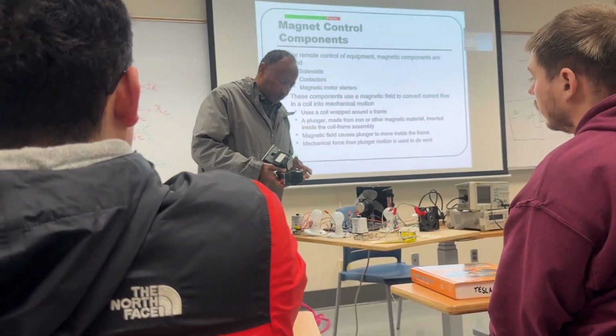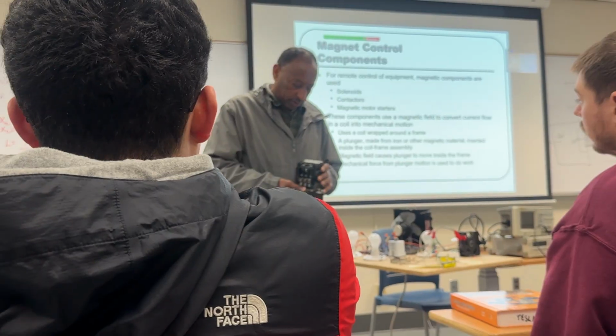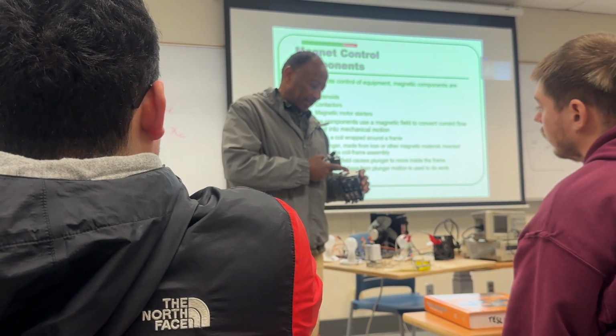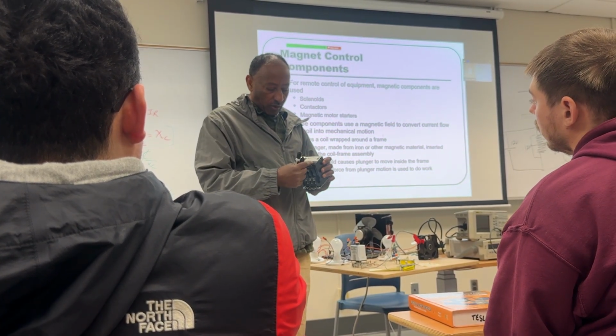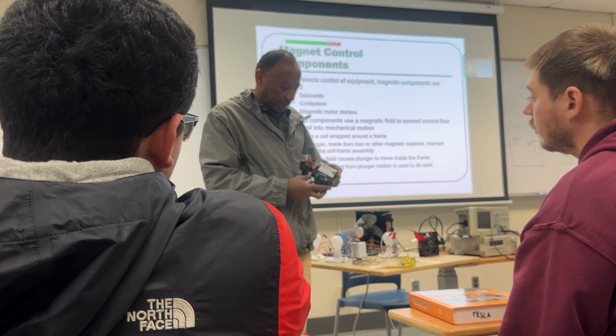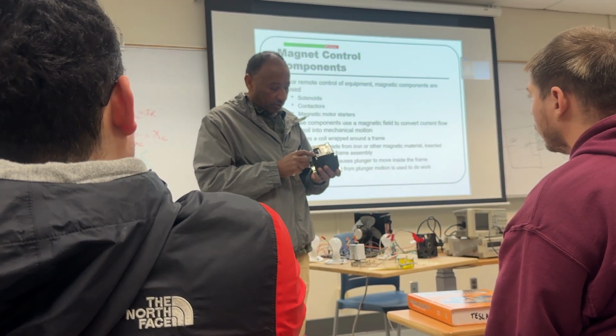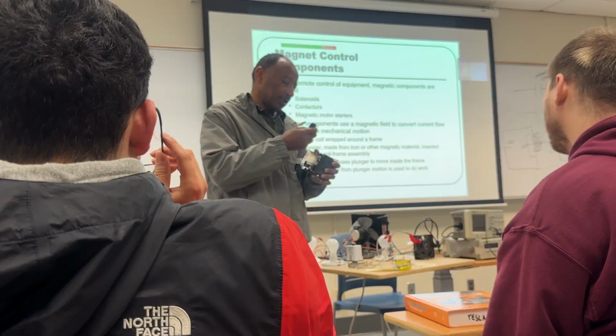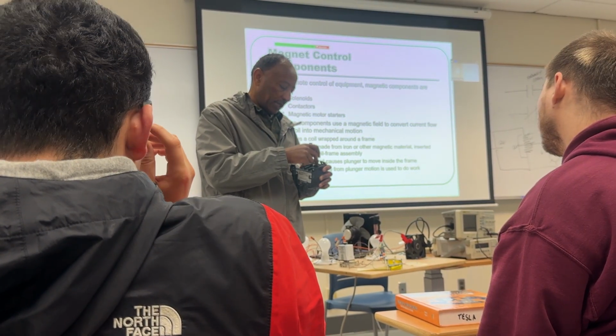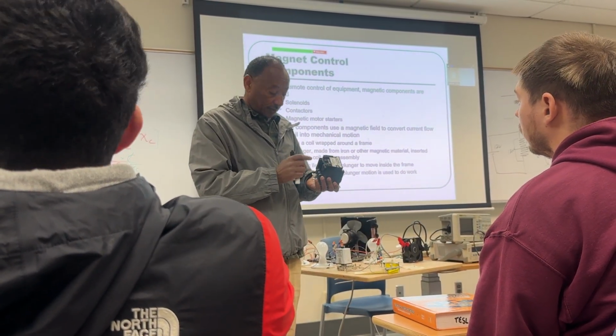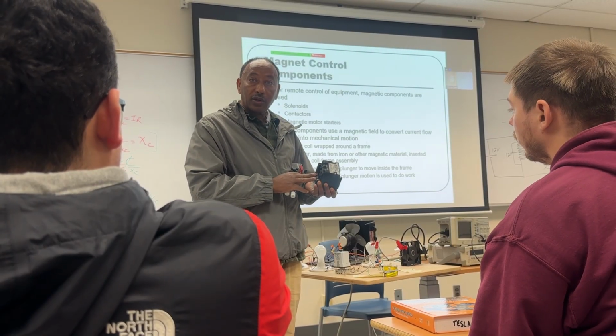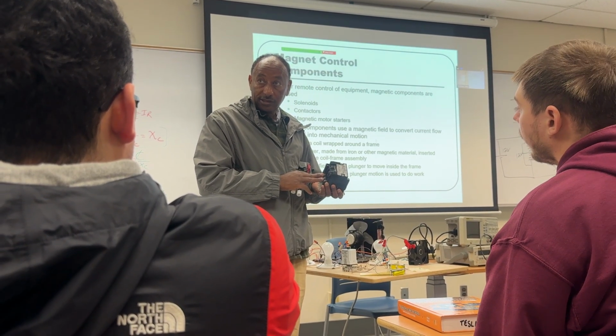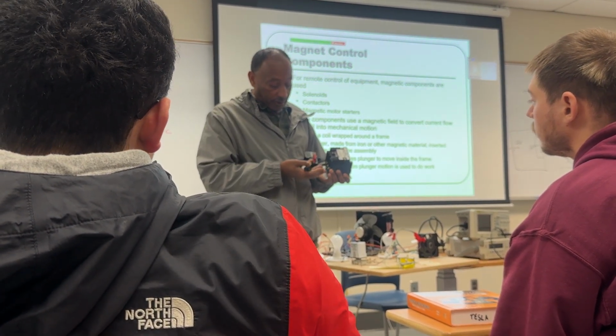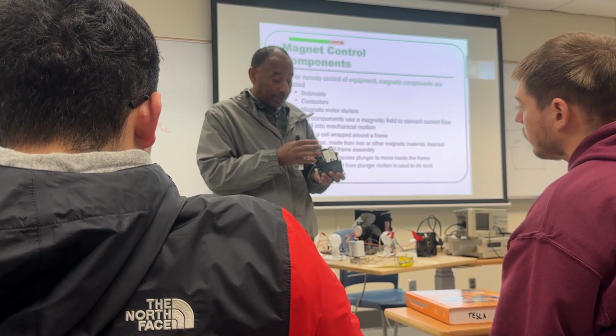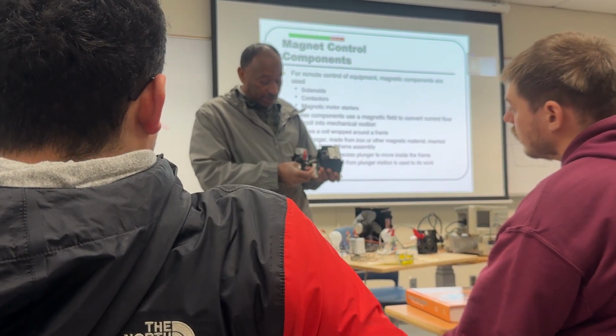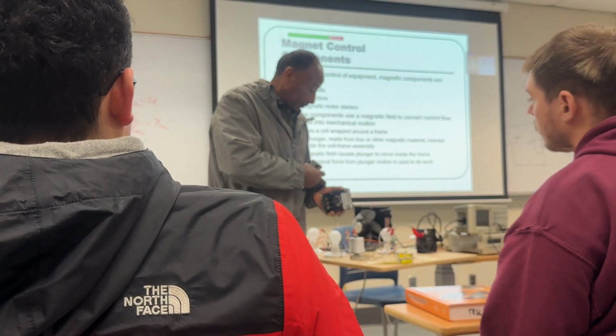This is usually used for 3-phase motors. You can see L1, L2, L3. This is what's called the coil. The coil is inside. When you activate this, it will close L1 and L3 and connect them, so the top and the bottom will be connected. You connect the power here, you connect the motor here. When this is activated, it will close this and connect the motor.